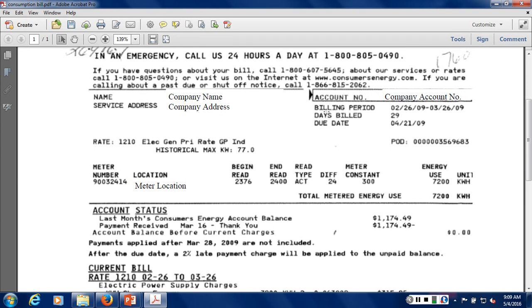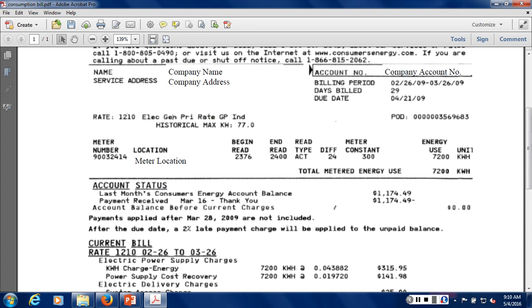Underneath the account information is the billing period — a range of dates from the start to the end of the billing period. This particular bill went from February 26th to March 26th, so the bulk of the days were in March; this would be considered the March utility bill. It covered 29 days of billing, and the utility company gives a due date for payment. Moving down, a crucial line is the utility rate — the tariff that this customer is on. This is rate 1210, described as an electrical general primary rate with the designation GP.